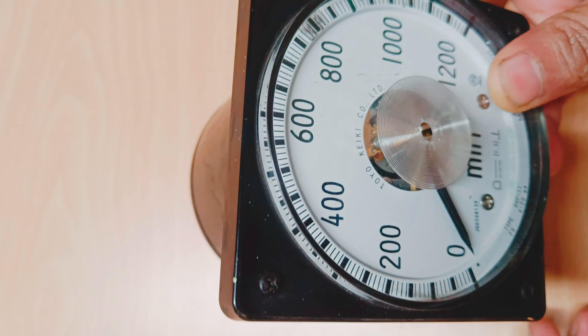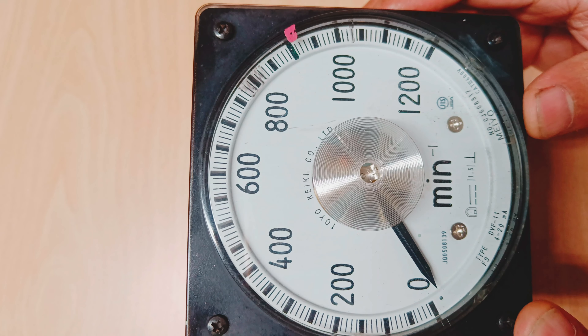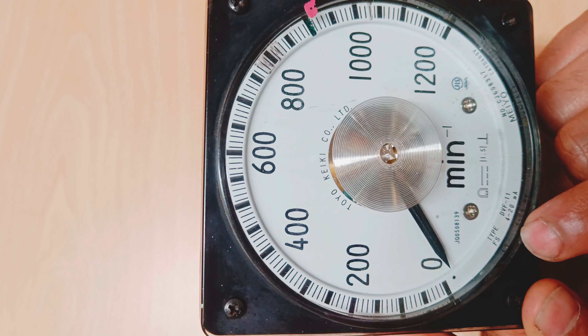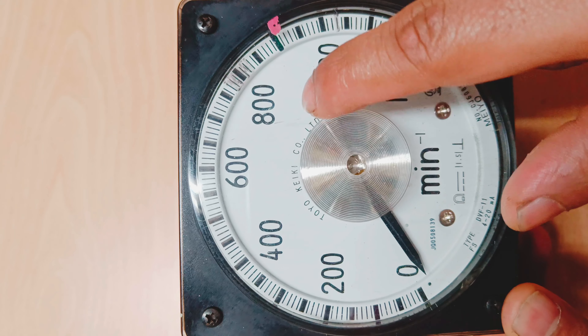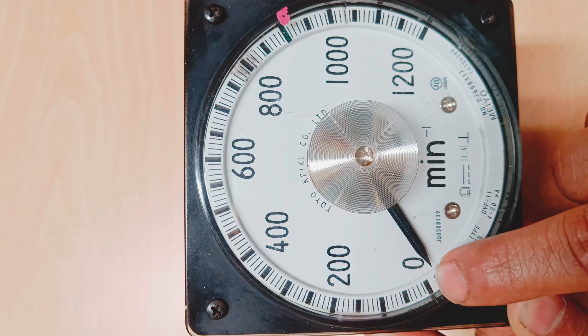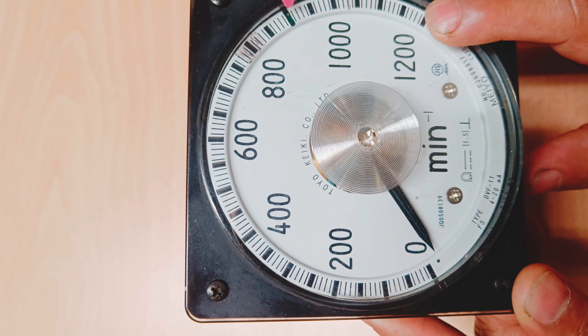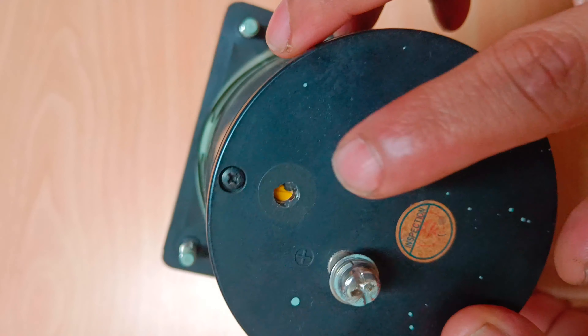Hello and welcome back to my channel. In today's video we are going to do the calibration of this tachometer. The range of this tachometer is from 0 to 1200 RPM. The full scale is from 4 to 20 milliampere and the maker is Toyo Keiki Company Limited. This means that at 4 milliampere the RPM should be 0, and at 20 milliampere the RPM should be 1200.